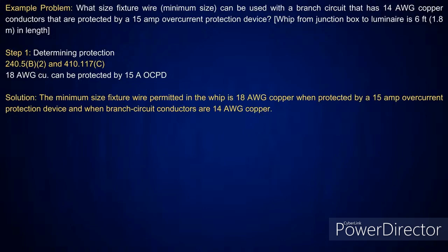Well, I've actually seen this before in luminaires, where they say you cannot take that 18 gauge to a fixture and then go from fixture to fixture to fixture, because it has to tap directly to that junction box. I agree with that, because if you're going from fixture to fixture to fixture and using that number 18, and you put too many of them on there, then that wire size is not large enough. That would be where I'd say there's a problem. I'm not necessarily calling it a tap, and I don't know personally the whole exact answer. I'm just saying from what I've seen, they're basically calling that a fixture tap to the branch circuit.